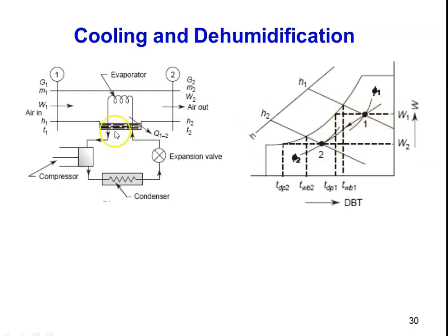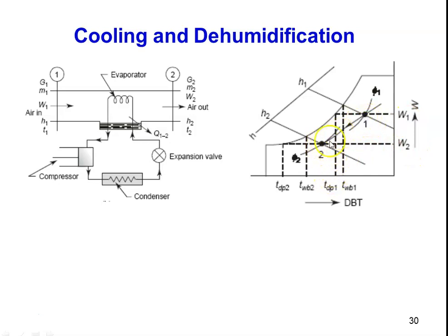The remaining components are the expansion valve, condenser, and compressor — this is a vapor compression refrigeration system where the evaporator coil is placed inside the air duct. On the psychrometric chart, the initial condition has specific humidity W1, enthalpy H1, and relative humidity φ1. The cooling and dehumidification process is shown as an inclined line: specific humidity decreases from W1 to W2, and temperature decreases from T1 to T2. This process is used in summer air conditioning.